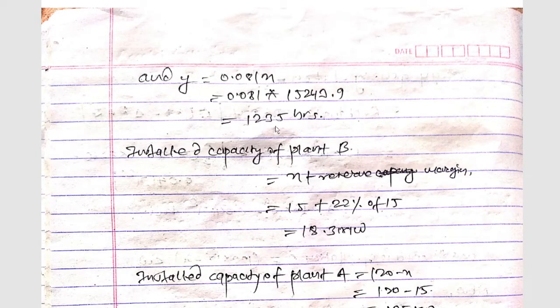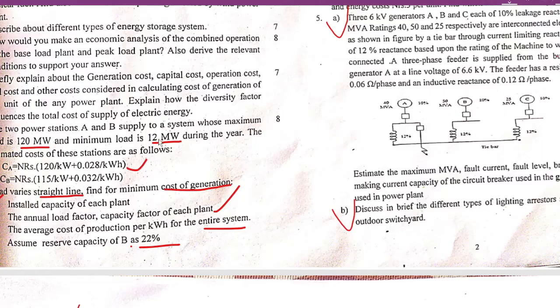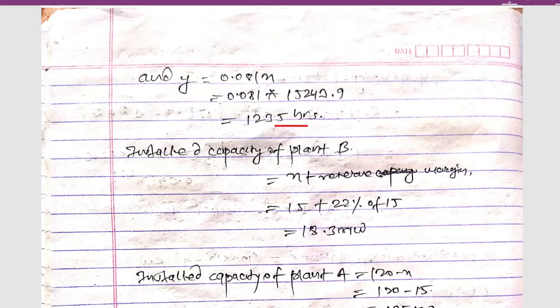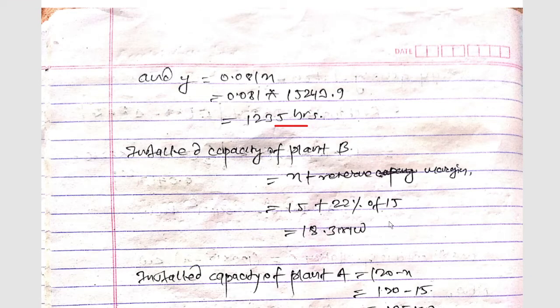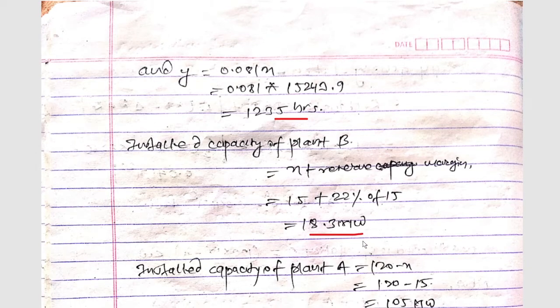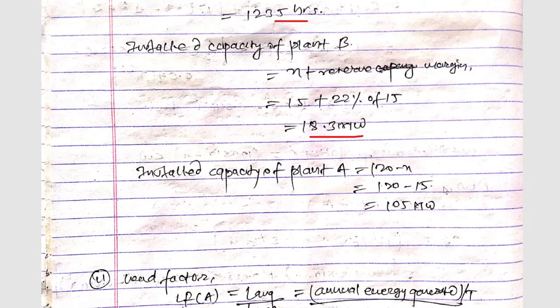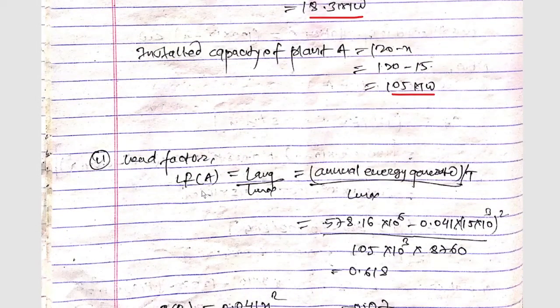The installed capacity of plant B equals X plus the reserve margin. Since reserve capacity is 22%, installed capacity of B = 15 + 22% of 15 = 18.3 megawatt. The installed capacity of plant A = 120 − X = 120 − 15 = 105 megawatt.